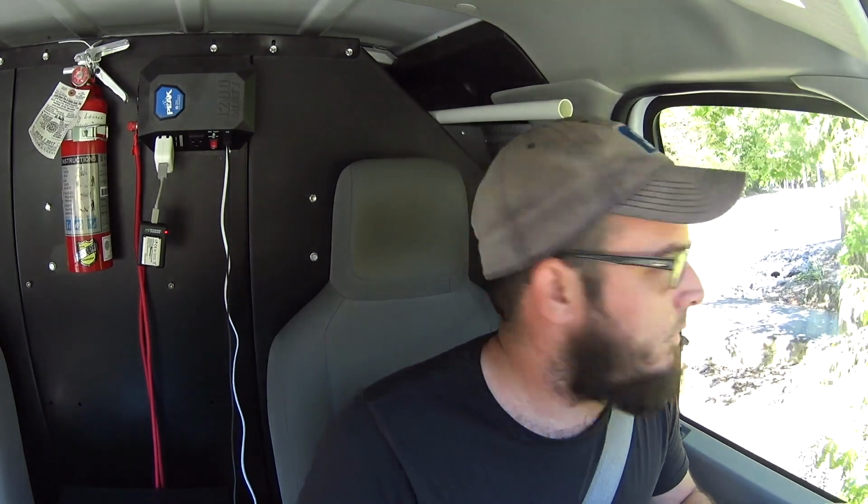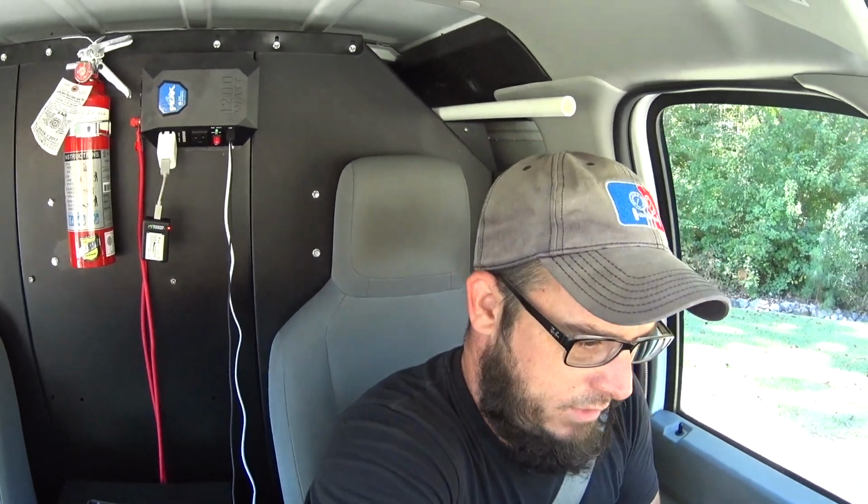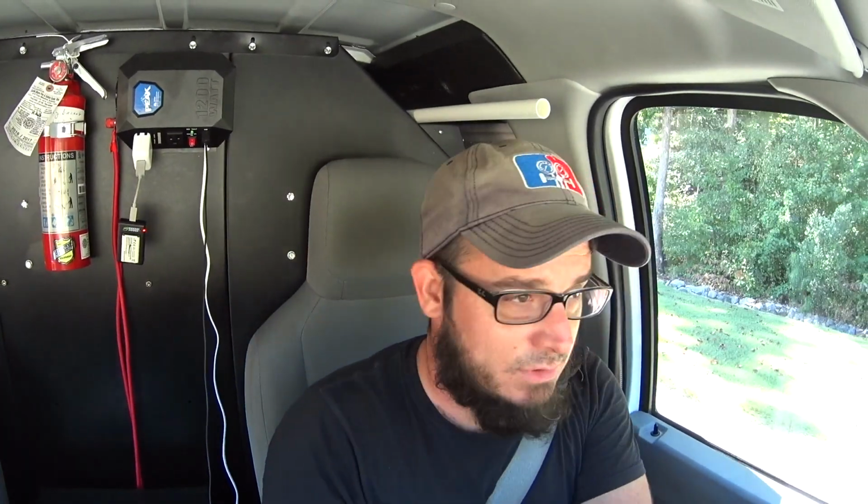I was down to about 1100 microns, and the reason I'm not terribly worried about the fact that I'm down to 1100 microns after an hour or so, even with the large evacuation hoses, is because I know that this system has had several poor vacuums pulled on it previously.